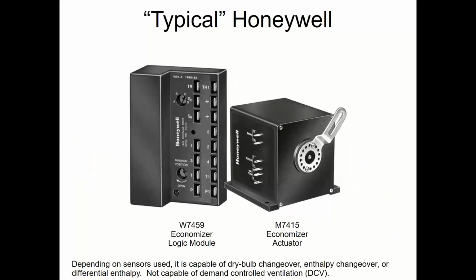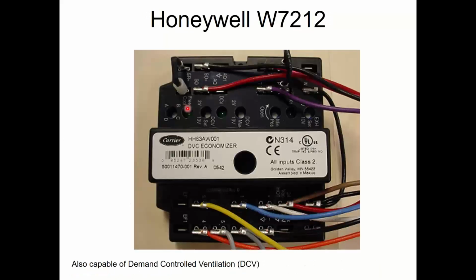A lot of the older economizers, you might only have two settings on there. Minimum damper position with a set screw. And then if it had enthalpy, I might have had an ABCD switch, which is the old version of curve 1, 2, 3, 4, 5. You probably won't see too many of these out there. I only pointed it out because if you see this one, you cannot add a CO2 sensor to it like we talked about last week for demand ventilation. It's not possible. You have to retrofit the controller. But if you have a rooftop that has this old of an economizer controller, that probably means your rooftop's pretty old, which probably means you're a candidate for replacing the rooftop like we talked about earlier.